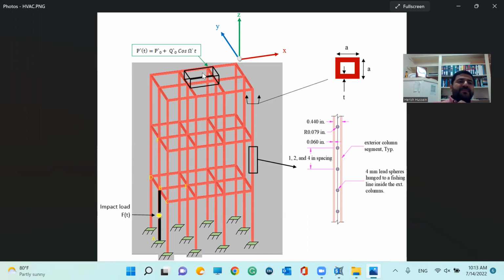3,890 pounds. No. It is 7,780 pounds for a 29-ton cooling tower from Baltimore Aircoil people. And I've divided it into 2, one going on this column, one going on that column. So when you divide that into 2, it will be 3,890. And that's for a real size building.